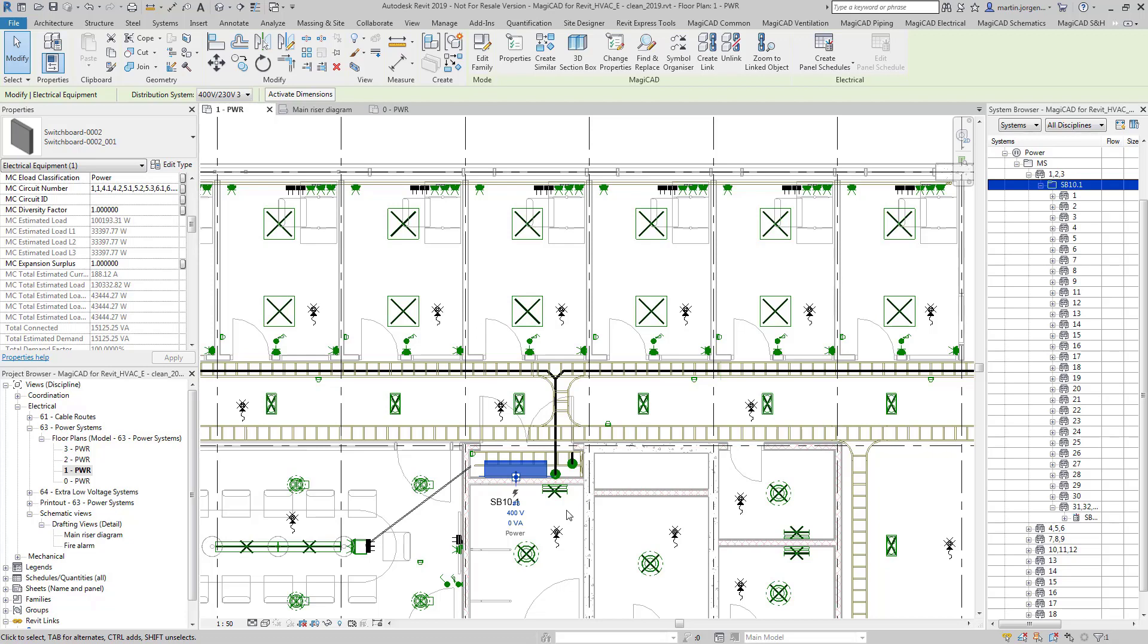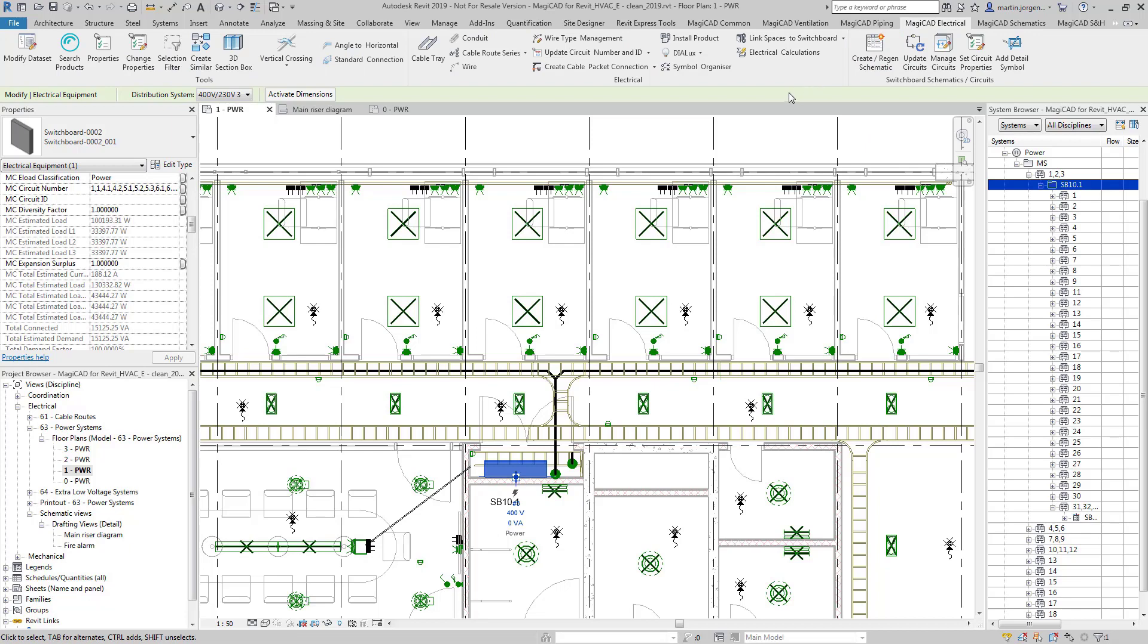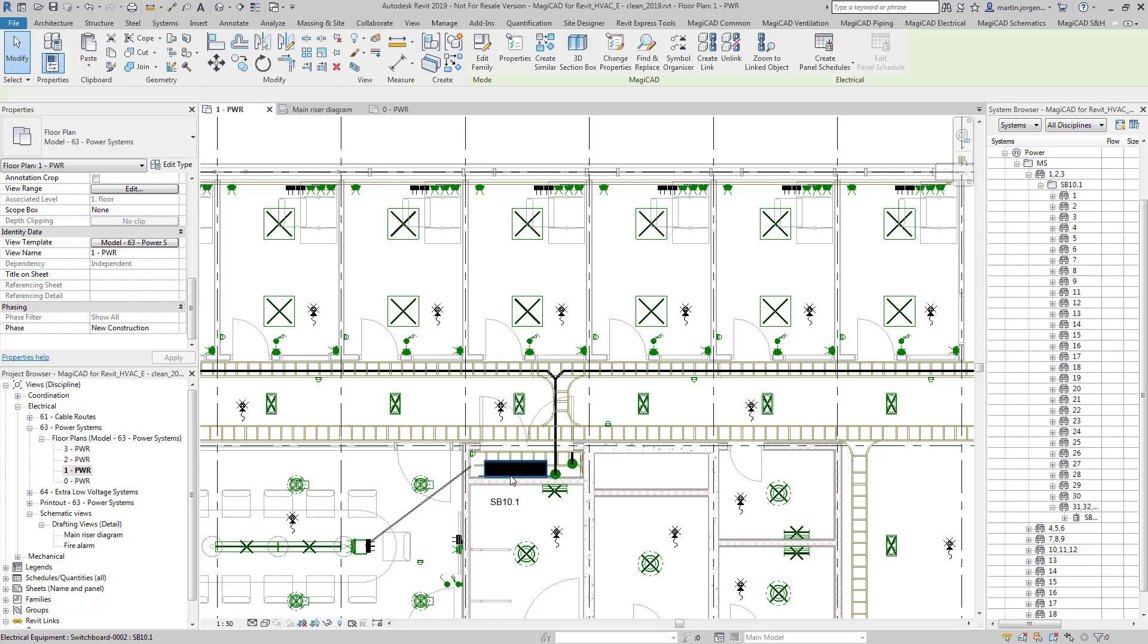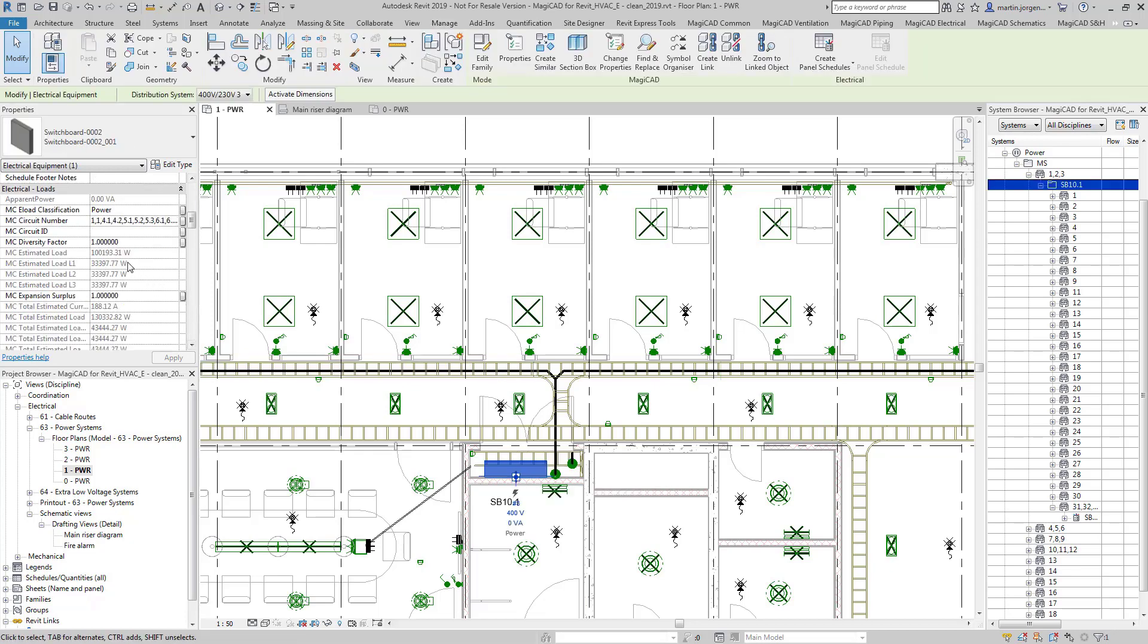What we've done prior to this is we've set up a number of spaces using the link spaces to switchboard feature and we've connected those spaces with early stage watts per meter squared load densities to the switchboard. At that point we can see here the switchboard now has this MC estimated load value, reporting just over 100 kilowatts for this switchboard.